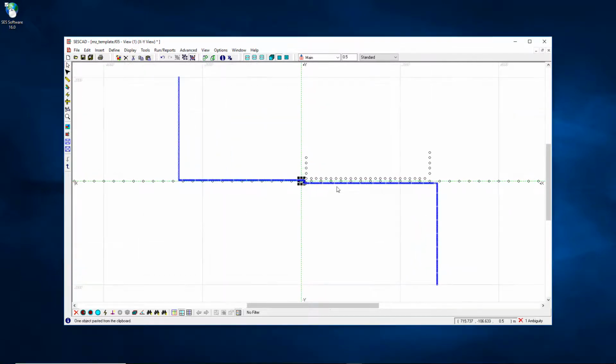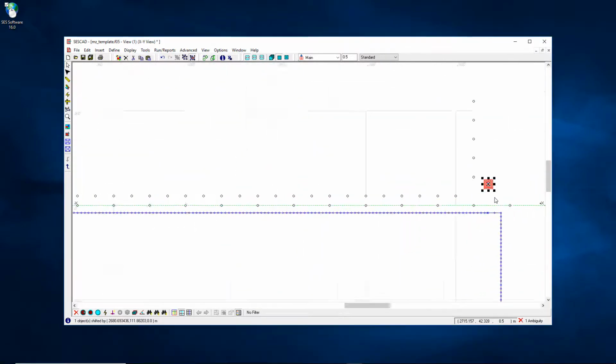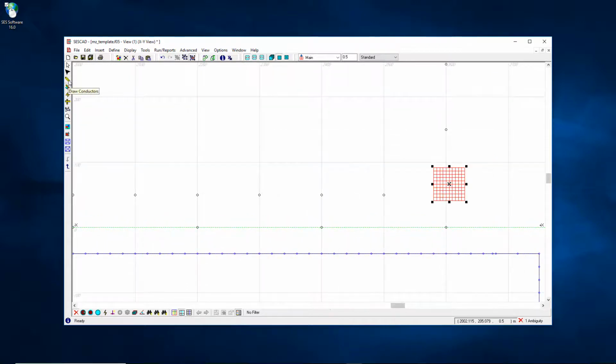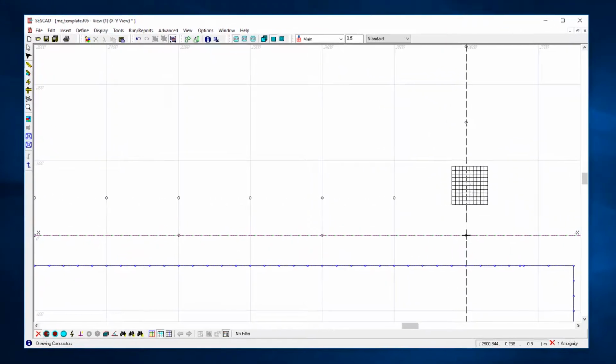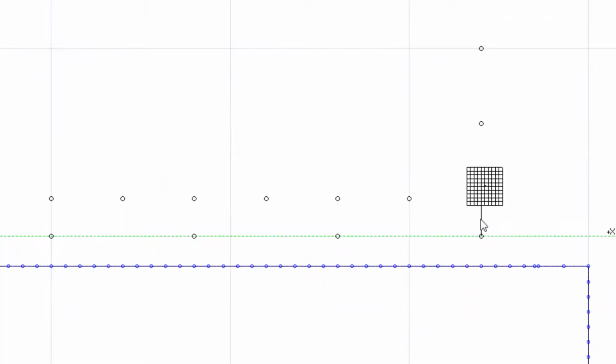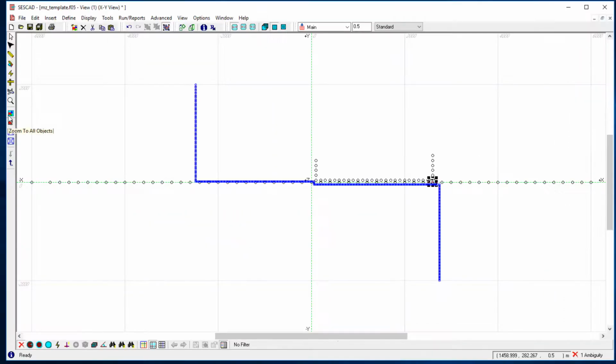Add the substation grid created at step 18 of Quick Start document at its correct location and connect it to the nearest tower that was exported by row. Here we want the connecting conductors to be coated with good coatings, in other words insulated, since MALZ only accepts below ground conductors. In a similar way, you can add the ground mat at the valve station site along the pipeline.